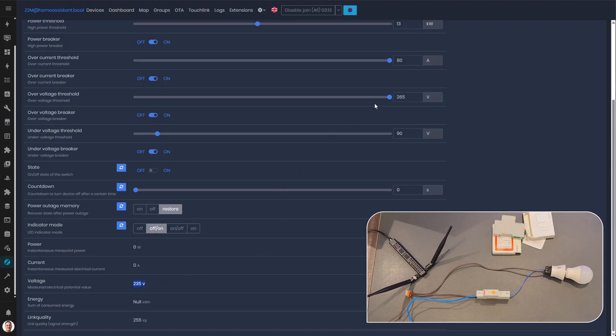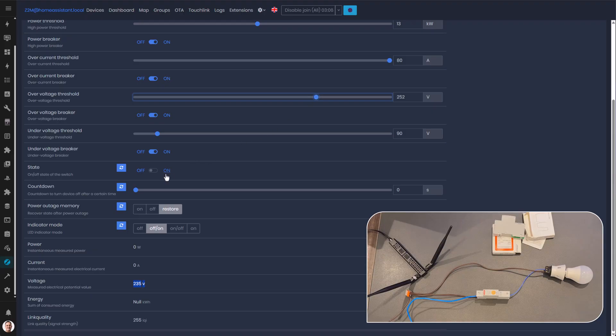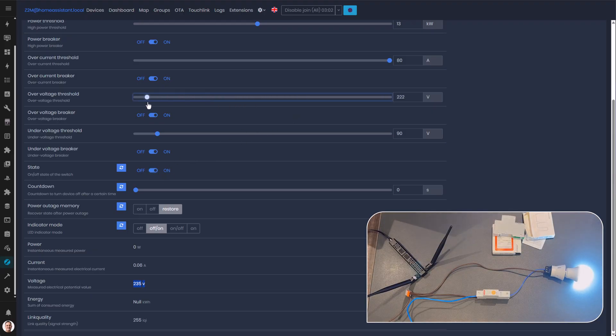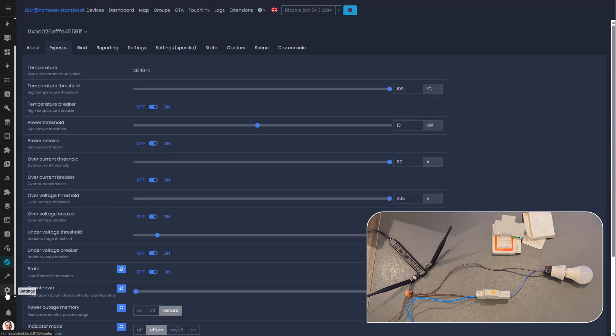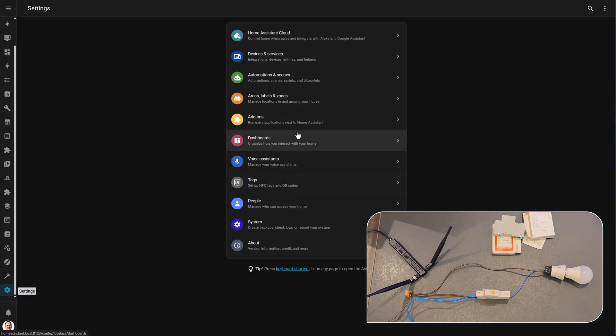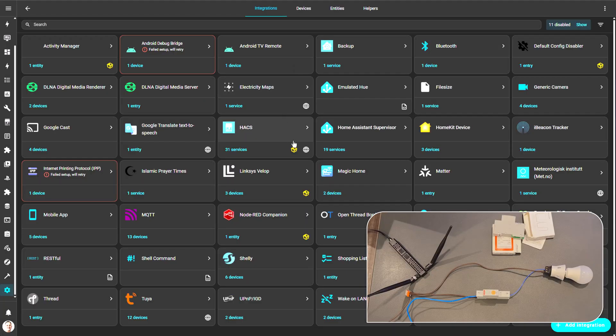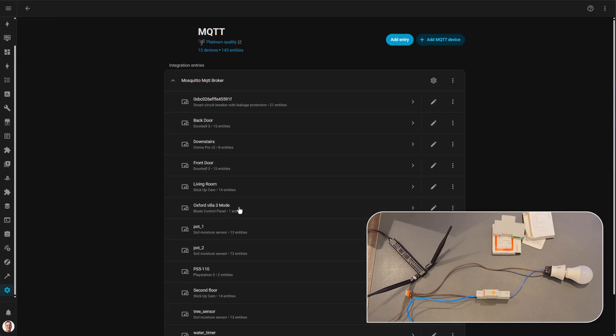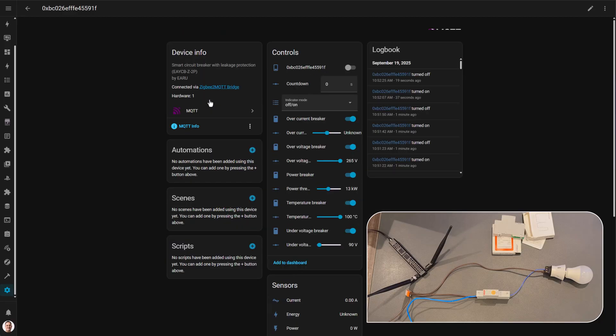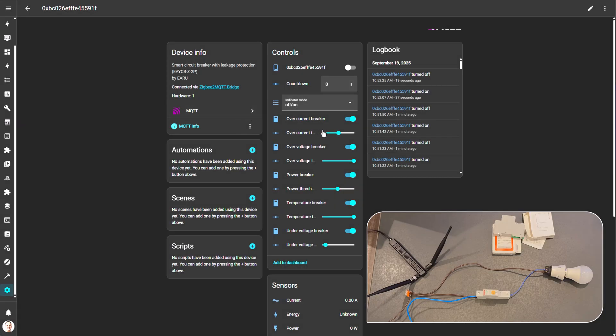It's reading voltage 235 volts. And now let's do one test for the over voltage breaker. We're gonna drag this down all the way to something that is below 235 and see if it will work. Okay, and it cuts the power. It's not as fast as we wanted it to be.